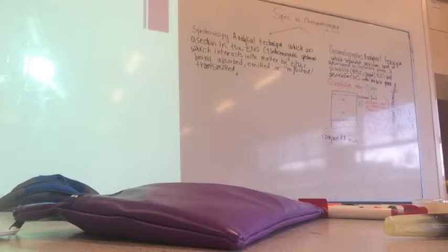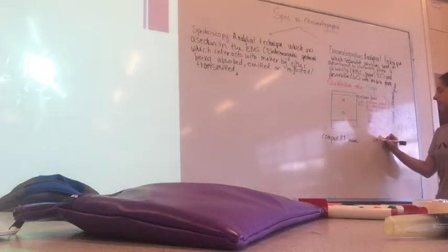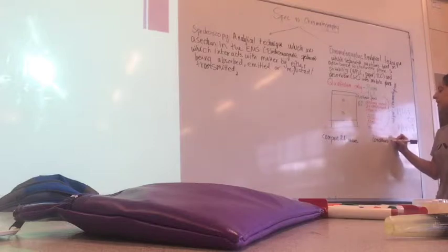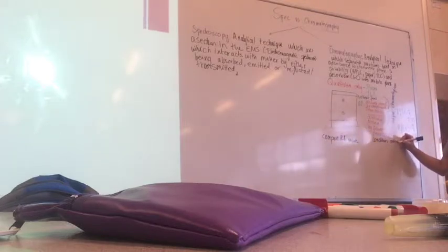What do you need to make sure you do to make the comparisons accurate? When you're comparing the RFs that you previously recorded or with a known sample or whatever you're doing. Yep, through the database. Yeah. Yep. You need to make sure that the conditions are the same. Excellent.